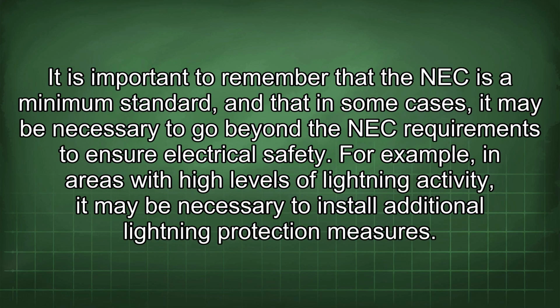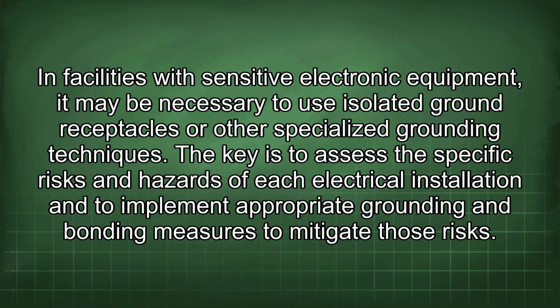It is important to remember that the NEC is a minimum standard, and that in some cases, it may be necessary to go beyond the NEC requirements to ensure electrical safety. For example, in areas with high levels of lightning activity, it may be necessary to install additional lightning protection measures. In facilities with sensitive electronic equipment, it may be necessary to use isolated ground receptacles or other specialized grounding techniques. The key is to assess the specific risks and hazards of each electrical installation and to implement appropriate grounding and bonding measures to mitigate those risks.